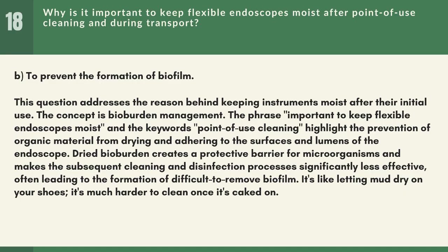This question addresses the reason behind keeping instruments moist after their initial use. The concept is bioburden management. The phrase "important to keep flexible endoscopes moist" and the keywords "point-of-use cleaning" highlight the prevention of organic material from drying and adhering to the surfaces and lumens of the endoscope. Dried bioburden creates a protective barrier for microorganisms and makes the subsequent cleaning and disinfection processes significantly less effective, often leading to the formation of difficult-to-remove biofilm. It's like letting mud dry on your shoes. It's much harder to clean once it's caked on.